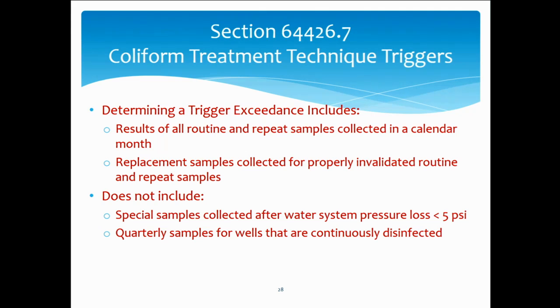Right. So there's a question of what about a campground with a full-time caretaker who lives there? The water system is pressurized year-round. There are provisions, we haven't gotten to that section of the reg yet, but there are provisions within the startup procedure for systems that are pressurized year-round where they can propose an alternative to what the requirements are for the startup procedures. So that's addressed. Because we know if it's pressurized year-round, it's not the same as if you've depressurized and you've had stuff from the outside leaking into your pipes. So there's a provision for that in the regulation.